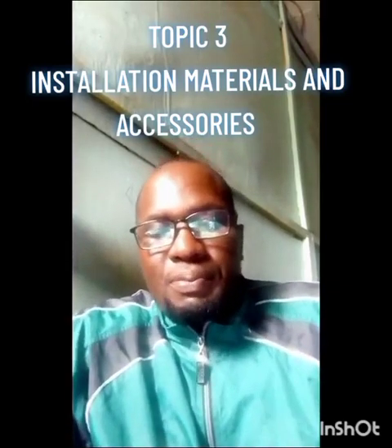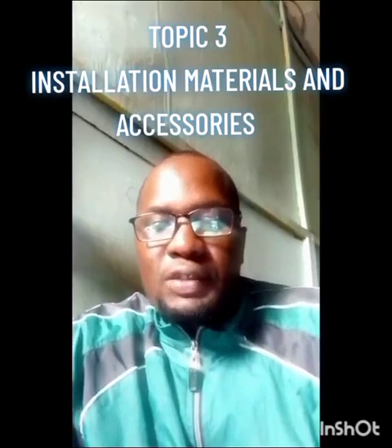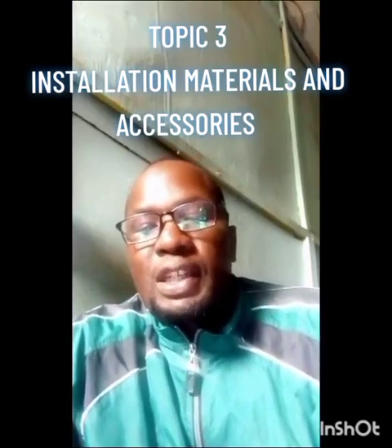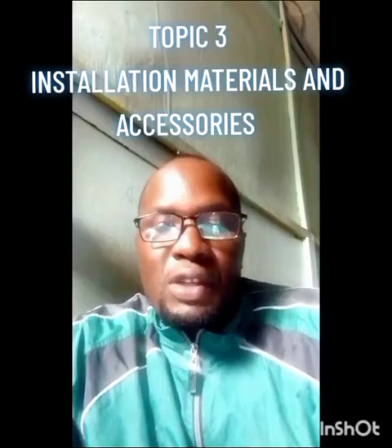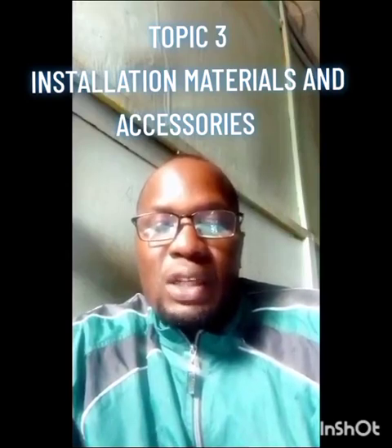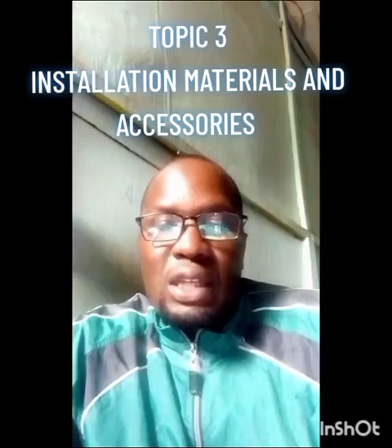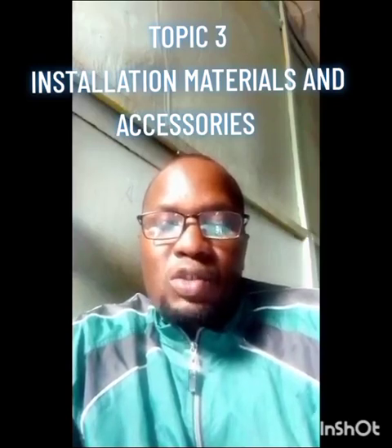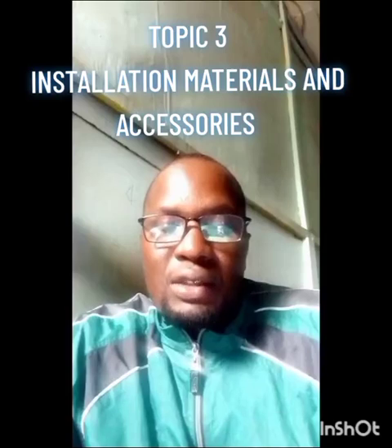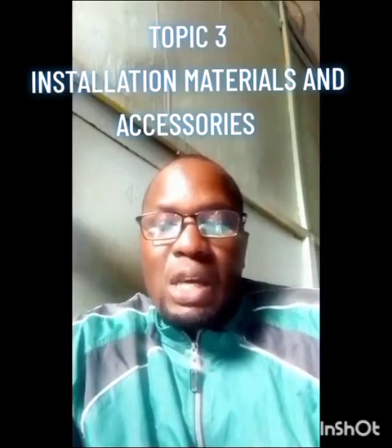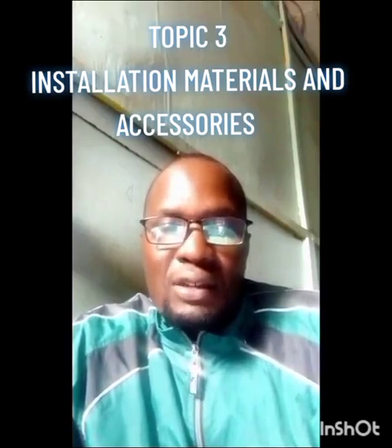Let's look at aluminum conductor. So it has 60% electrical conductivity as compared to that of copper, and it's light in weight. It's affected by surrounding atmosphere. Its soldering is somewhat difficult. It can also be made into wires, but they are not as strong as copper wires. To make it strong, a steel wire is used in the center of the stranded aluminum conductors. The conductor is then known as aluminum conductor steel reinforced, that is ACSR.